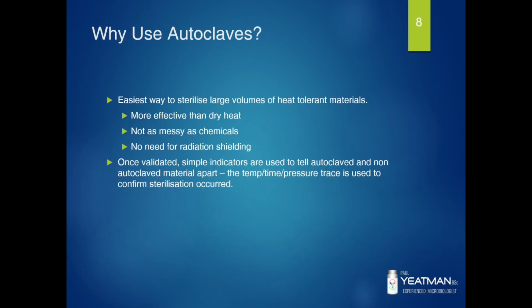Why use an autoclave? Well, it's the easiest way to sterilise large volumes of heat-tolerant materials. So I'll discuss why it's better than dry heat and chemicals and radiation. Why is an autoclave better than dry heat? Steam penetrates better than heat radiation, and it's also faster at killing than dry heat. Steam also is not as high a temperature as dry heat, and it won't burn many substances despite having a lot more thermal load than hot air. For example, you can sterilise filters in an autoclave. Using a dry heat oven would result in char.